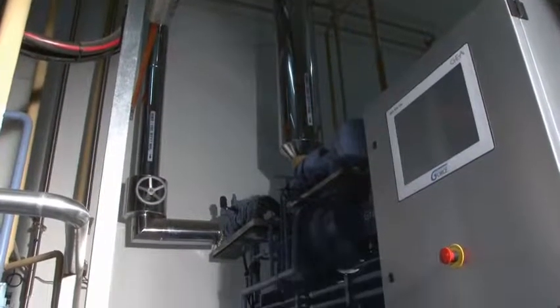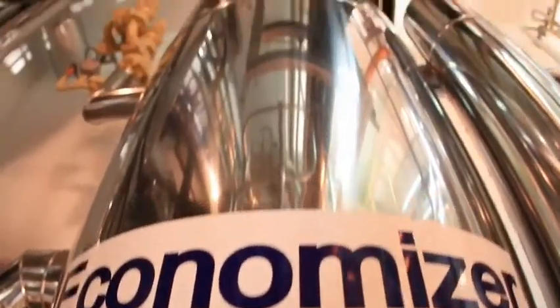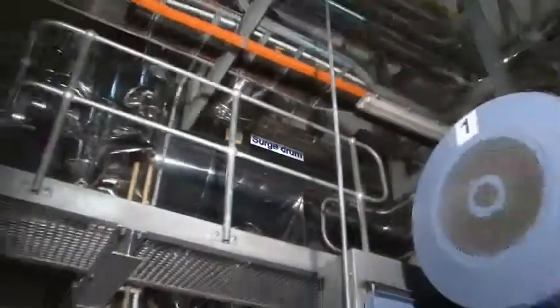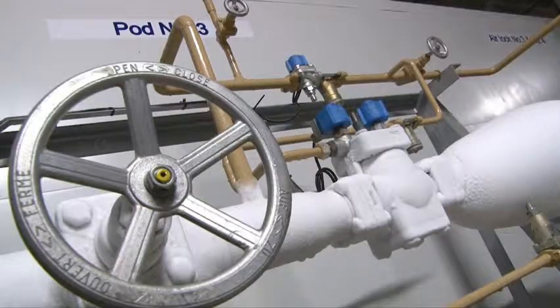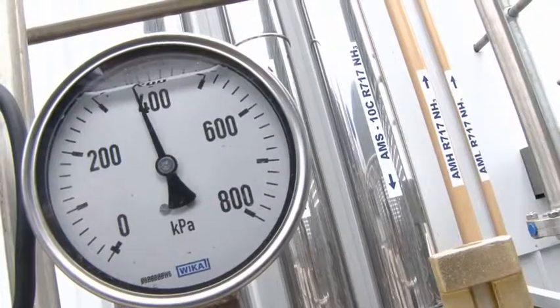The WSP design consists of a single-stage ammonia R717 system operating with an economizer and a side load for airlock cooling. Energy conservation is taken very seriously at Ayoba Cold Store. All electric motors throughout the refrigeration plant are set to operate on high efficiency. Four freezer pods come equipped with hot gas defrost and other energy-saving initiatives like heat recovery for domestic water and underfloor heating.